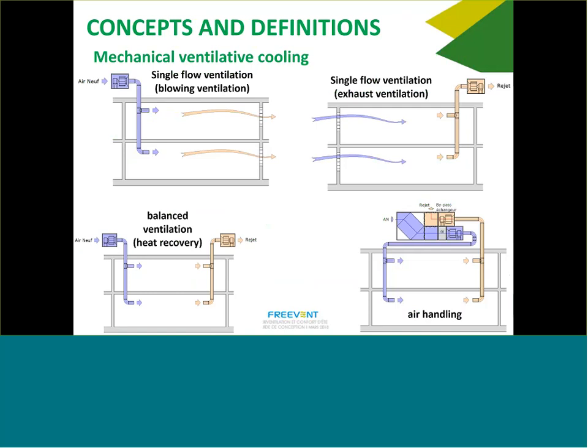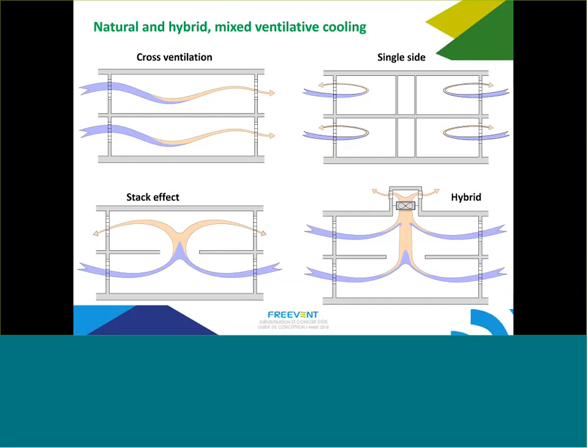I will come back on a few of these items. In mechanical ventilative cooling, you have either supply or exhaust single-flow ventilation, or double-flow balanced ventilation with heat recovery. Because nowadays, at least in France, we can't do balanced ventilation without heat recovery. Of course, when we do ventilative cooling, we need to bypass the heat recovery exchanger. In natural ventilation, you have either cross-ventilation — where you can have a cross-airflow and get the most from the system.